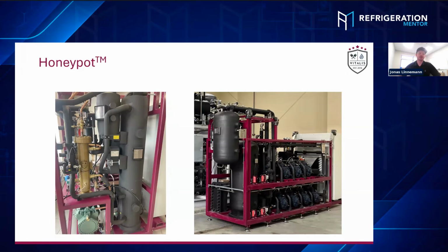So I always recommend to fill the oil while you're pulling the vacuum because that's the easiest. You don't need to have perfect pumps and stuff to pump it against the internal pressure. And in case you have some water dissolved in the oil, before it builds the toxic, the poison part, you're still able to vacuumize some moisture out of the oil. So it's not bad to have that pulled into the system while initiating the vacuum for the whole system.